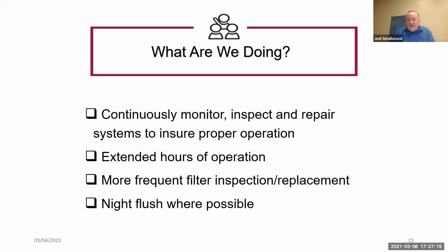And as Mike talked about really early on, we then had a bunch of wildfires that sent a lot of people home and sent a lot of smoke inside our building. We were basically pumping the air that you have outside into our buildings, and that causes a lot of issues. So we had to back off on that for a while. And then wintertime got here, so we had to back off to a minimum setting, if you will, on that outside air. Still bringing in outside air to meet code, to meet the requirements of the buildings. We're actually a little above what our absolute minimum could be on outside air right now.